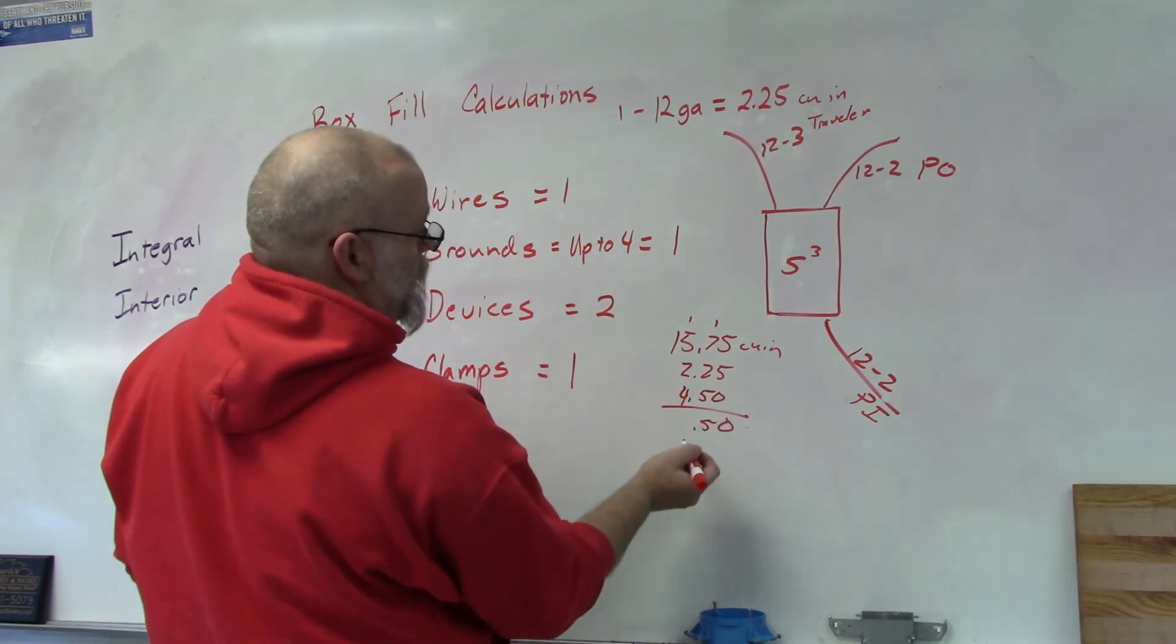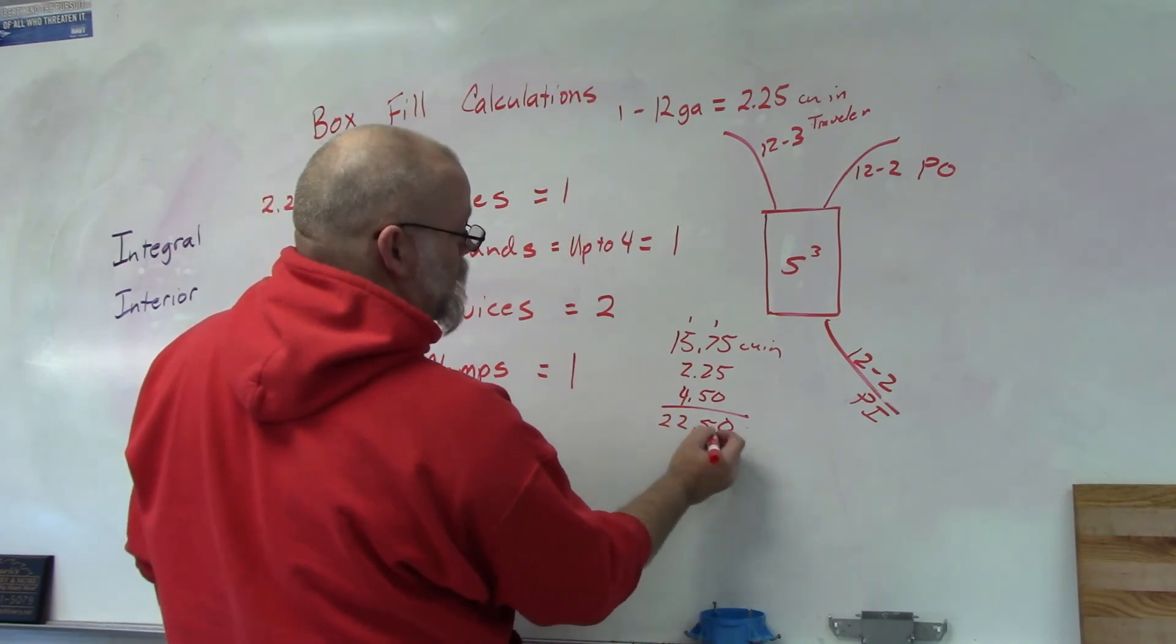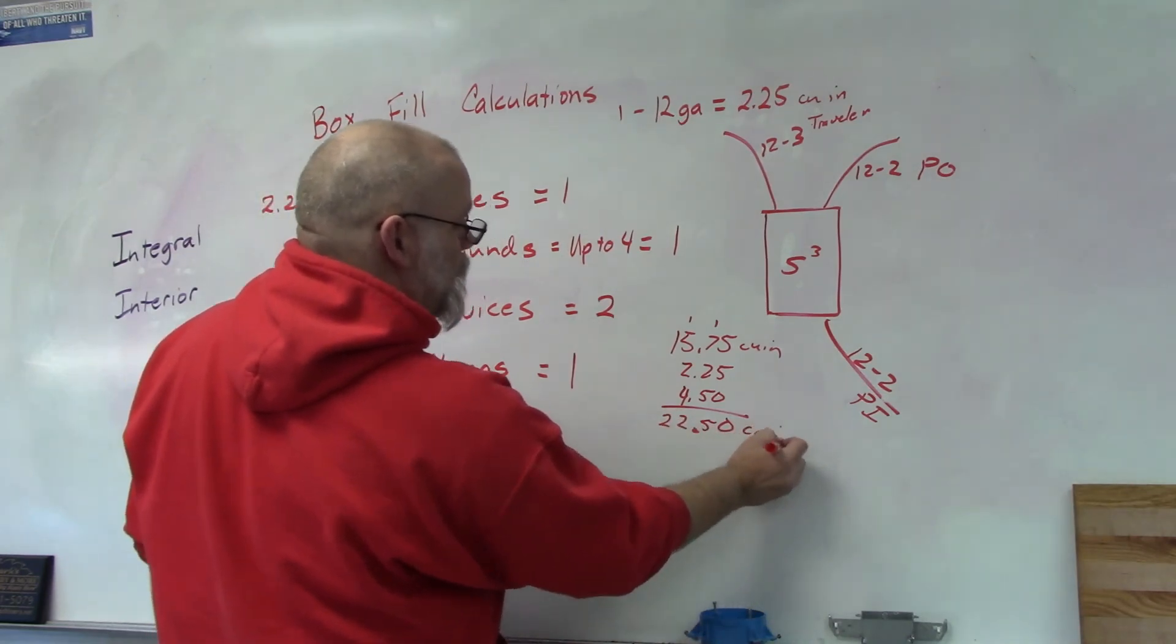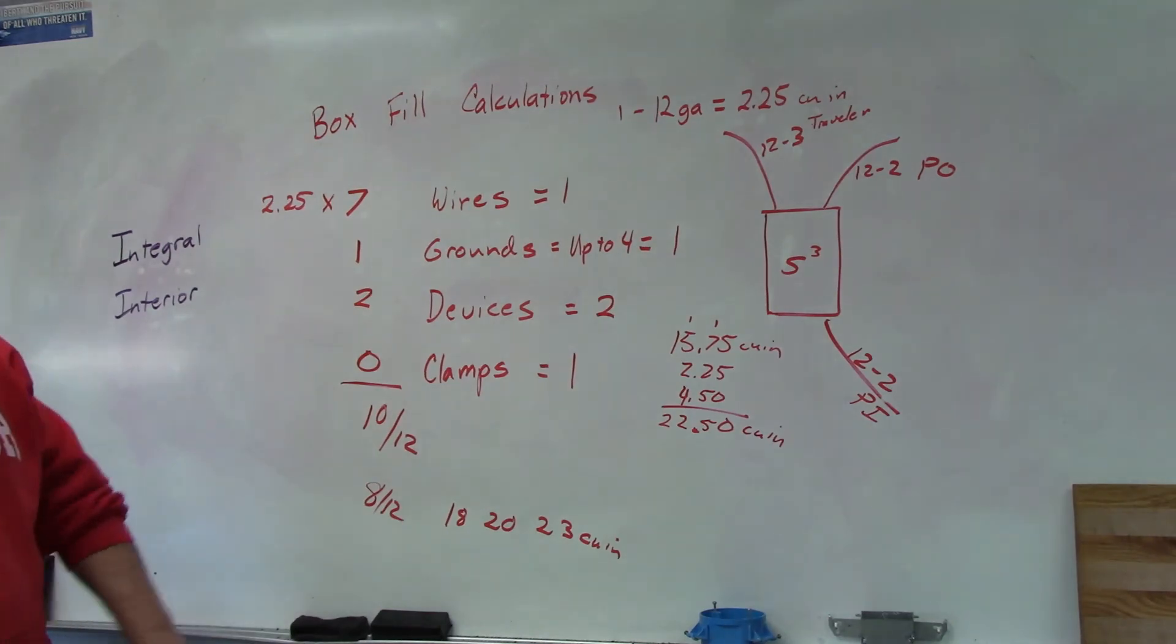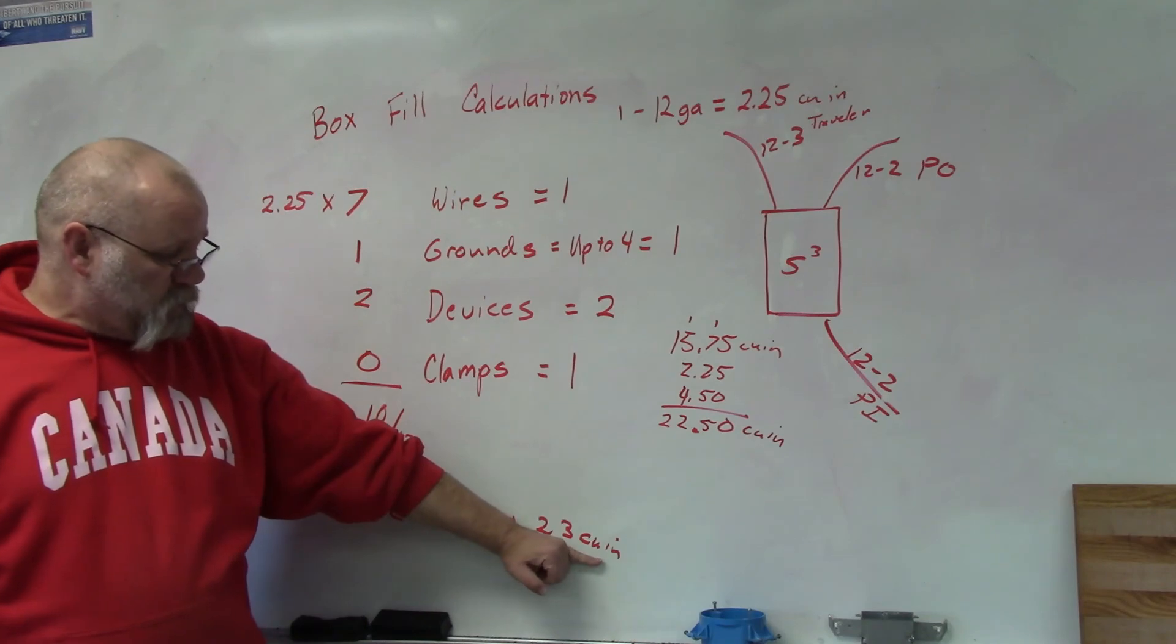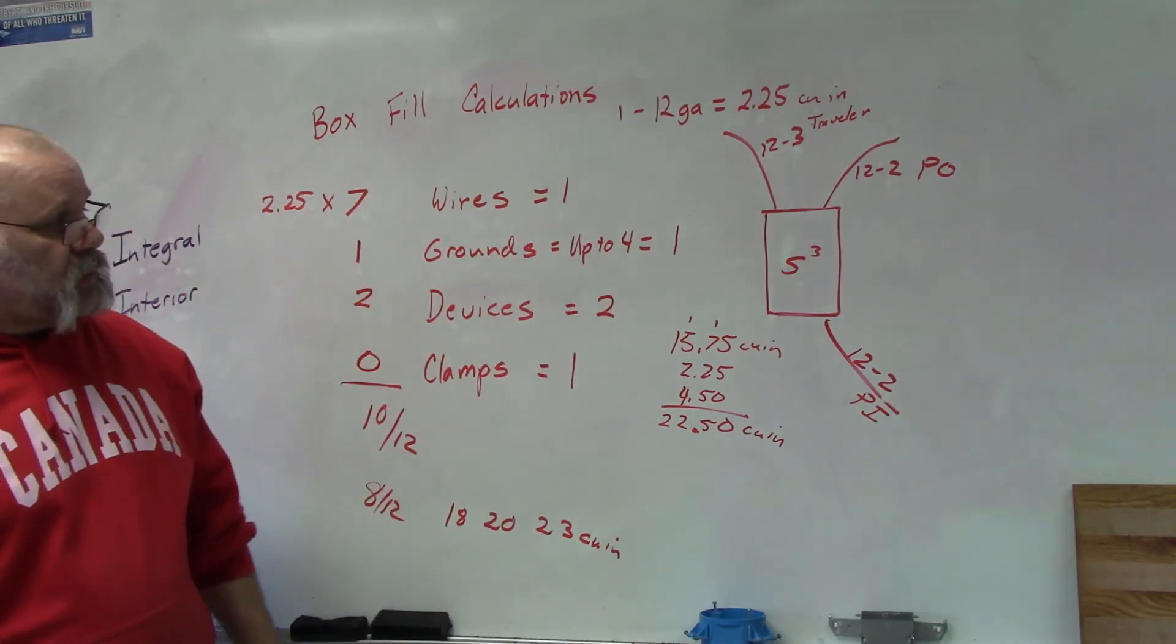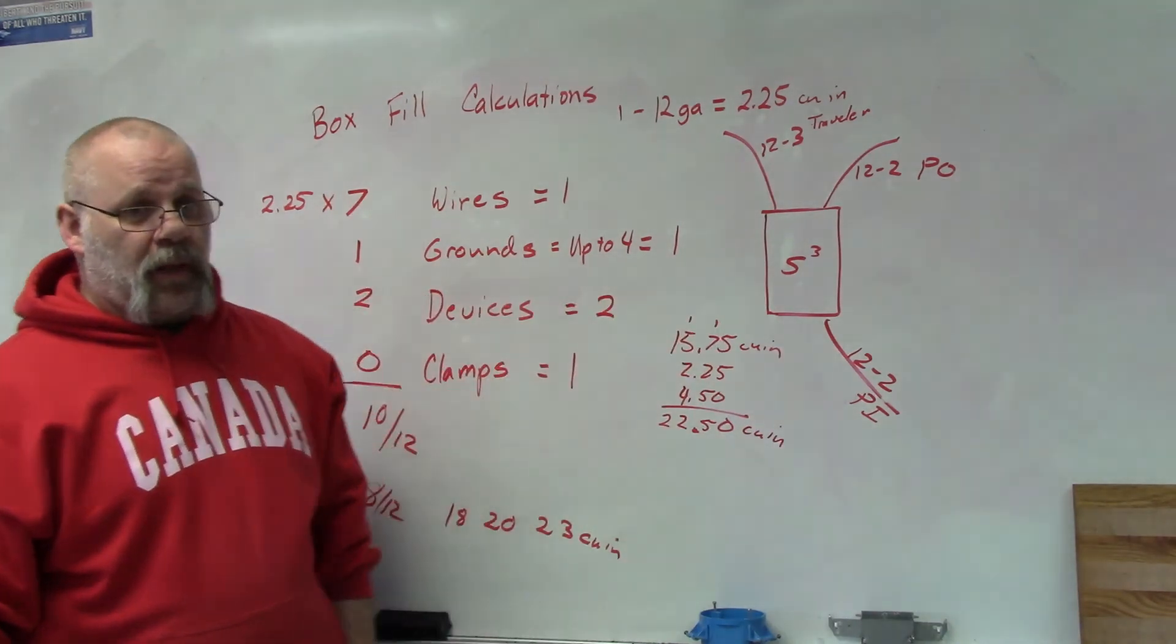If I add them all up, 15.75, 2.25, 4.5, 22.5 cubic inches. So in order for this setup to work, I would have to get the largest 23 cubic inch box in order to run this wiring setup for a three-way switch.